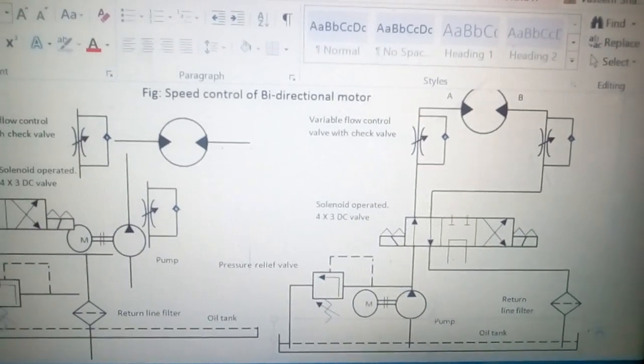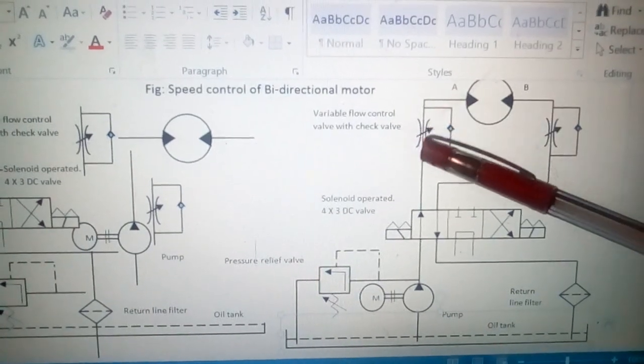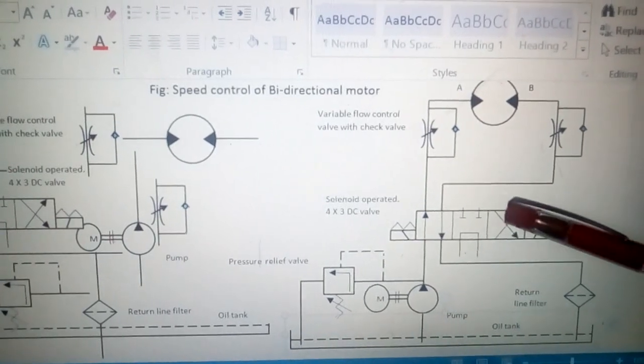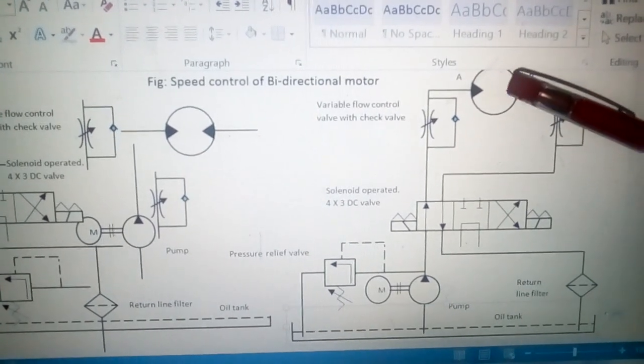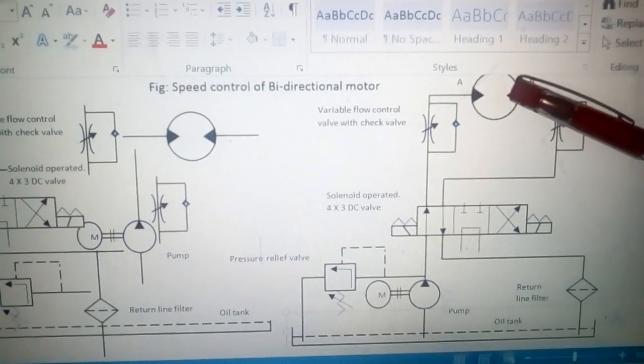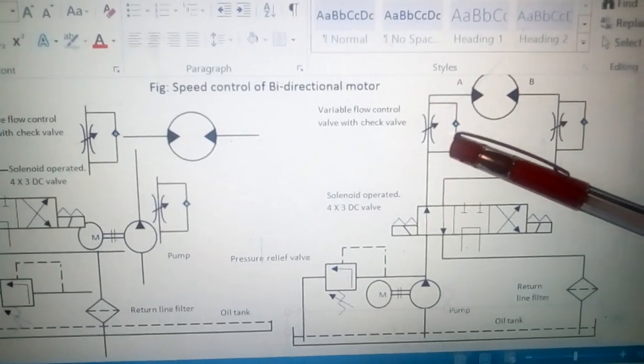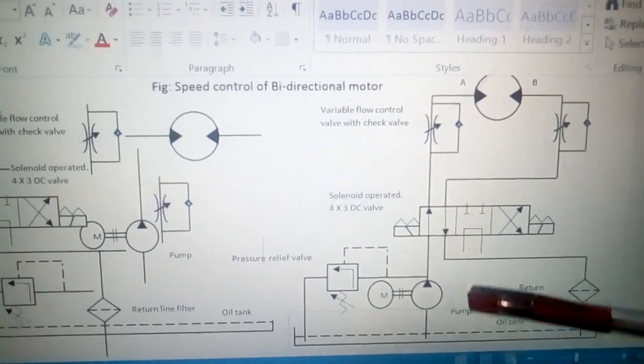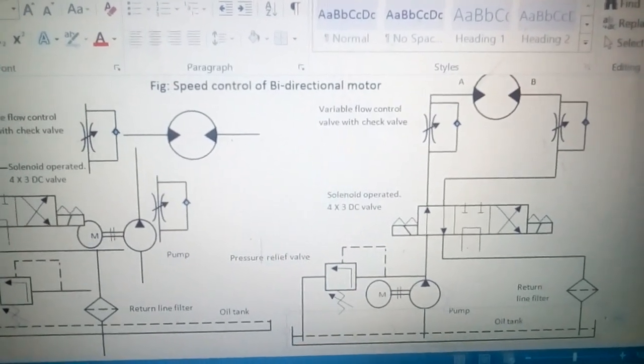In summary: position one — the motor rotates clockwise with speed controlled by the flow control valve; position two — oil goes to port B, the motor rotates anti-clockwise with flow controlled, and used oil returns via the check valve to the tank; position three — oil returns directly to the tank with no rotation of the motor.